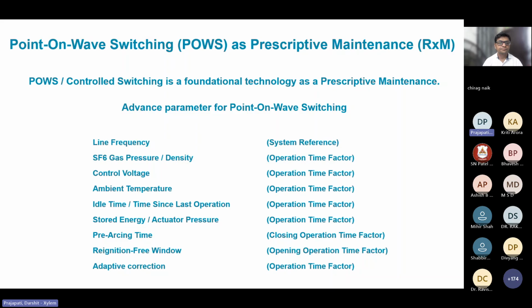And this can be done with the auxiliary contacts available with the breaker. It then uses the error to automatically adjust the timing delay for the next operation, thereby tracking the long-term changes like mechanical wear and aging, which are not covered by the four major parameters. So this will be taken care of by this adaptive correction. Those not addressed apart from the listed parameters will have an impact on the timeline, and that can be cumulatively adapted over a period of time by this adaptive correction algorithm.